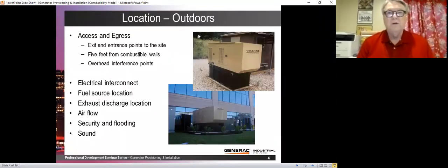All right, location. So this seems easy, but it often is one of the more difficult things we have in terms of installing a generator, is figuring out where to put it. So you need entrance and exit points from the site. We have 5 feet from combustible walls. Now let me talk about the 5-foot rule a minute. Generally, inspectors, if they are familiar with generators, are going to have the 5-foot rule in their brain, and they're going to want the generator 5 feet from everything.